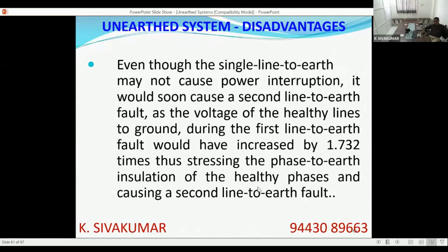So even though we said that there will not be any power interruption during a single line to ground fault, it is a big advantage. Practically it is not so. Even though the single line to earth fault may not cause a power interruption, it will cause a second line to earth fault sooner than later, because the ground potential has now become phase potential during a single line to ground fault.